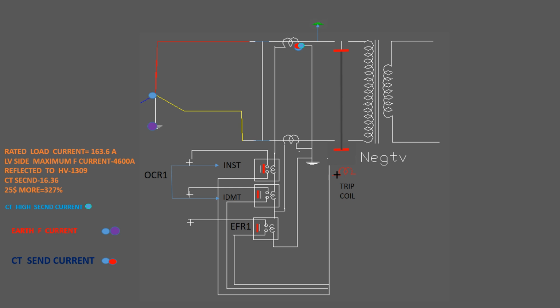That means the HV side double pole circuit breaker and the LV side single pole circuit breaker, and the transformer will be dead. It is dangerous near the part of an earth fault. So it has been designed, and all these things are programmed in the microprocessor relay.